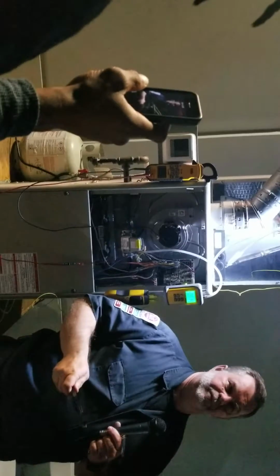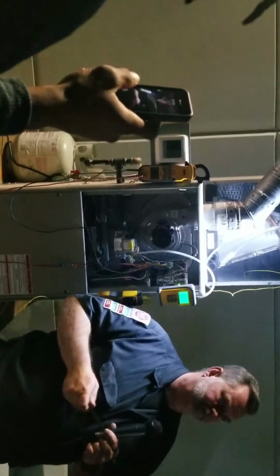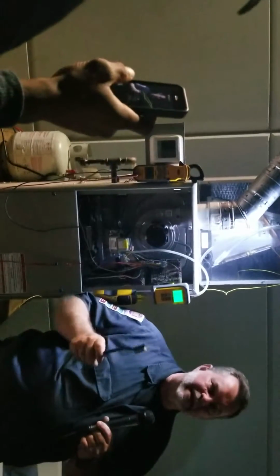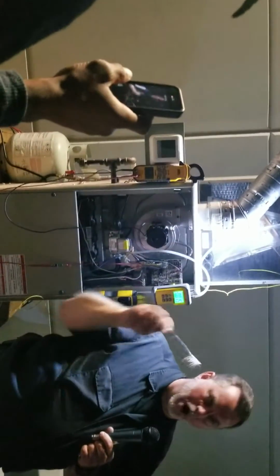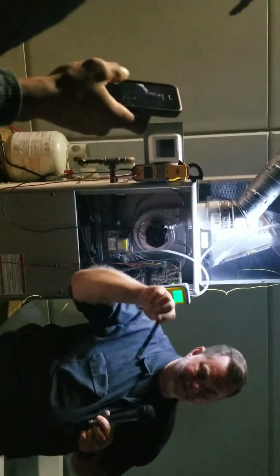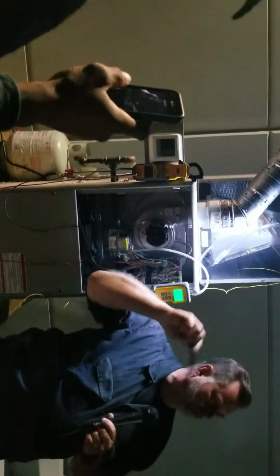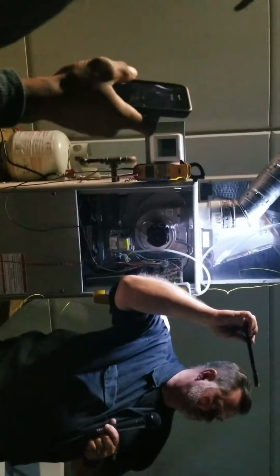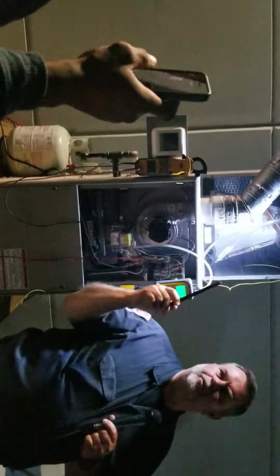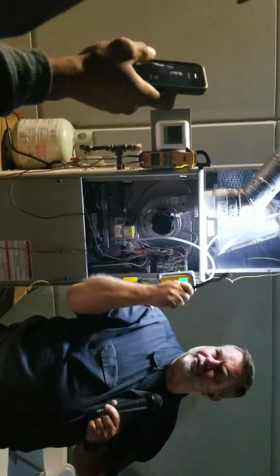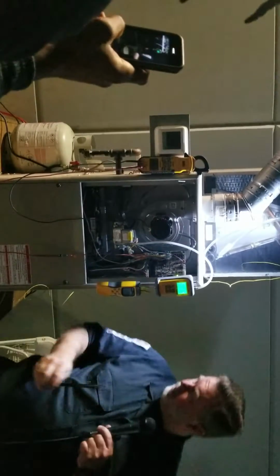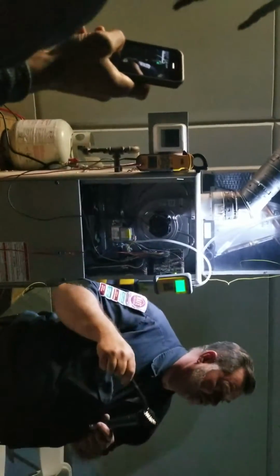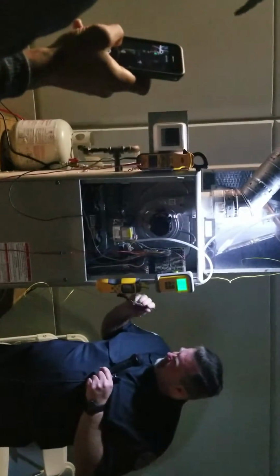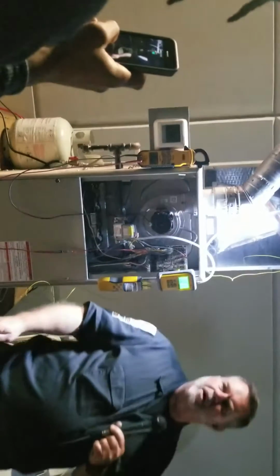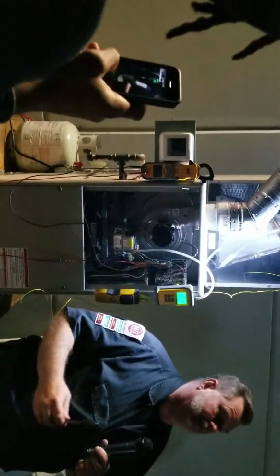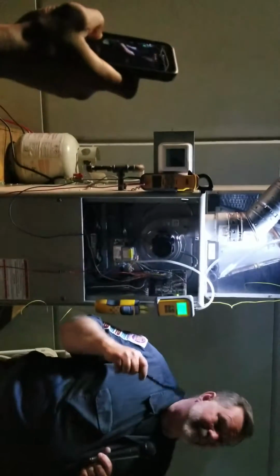Do not use a dollar bill. Do not use sandpaper. The reason is it leaves a residue on the rod, and that residue, when you put it back in the flame, will become burned and leave more residue. This doesn't leave any residue, and it's cheap. And I've done service calls where all I had to do was scratch this with this toothbrush, and that's all I had to do. You just get in there and you scrub it, basically. Some of them you get to really easy. This one you can't get to really easy, but it's only got one screw. You have to remove the rod on this one. Some of them you don't have to. It depends on how easy it is to get to. Does that make sense? No sandpaper.